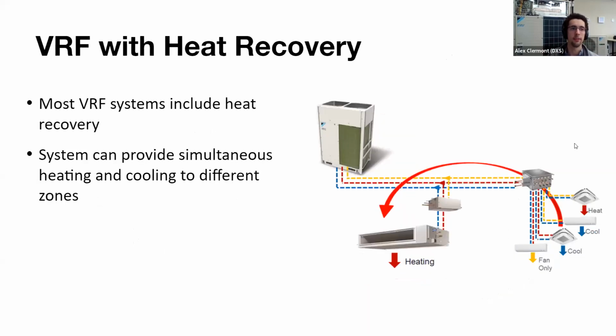Next, we'll get into VRF systems with heat recovery. With heat recovery, you can have different indoor units in different modes, essentially. So one indoor unit could be heating while another one's in cooling. There's an extra component here that you'll notice, and it's those branch boxes. Those branch boxes come in various different shapes and sizes, and they are essentially the traffic cop for refrigerant, and they let either liquid or gas through depending on what's required by the indoor unit. This is usually the most common type of VRF system used in commercial buildings. It does depend on what type of space it's serving, but oftentimes it's preferred by the owner or the tenant to have that flexibility to be able to go into heating or cooling.